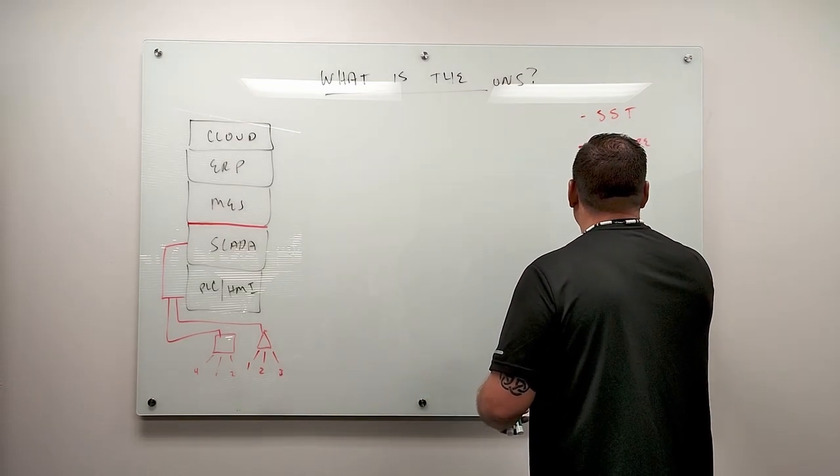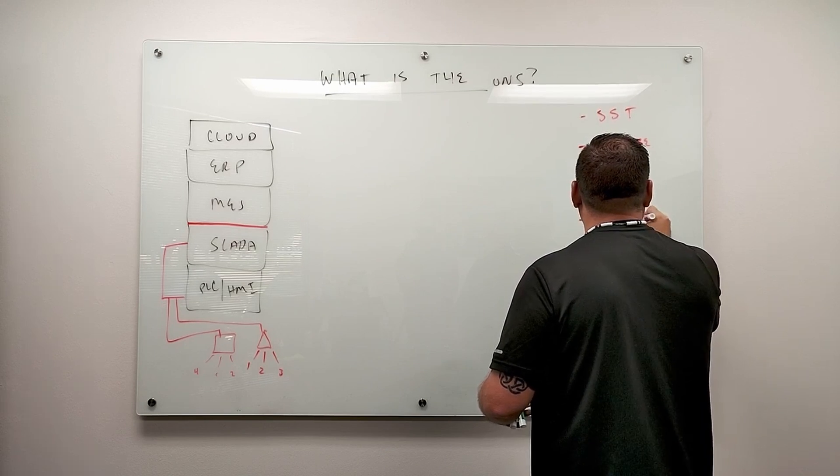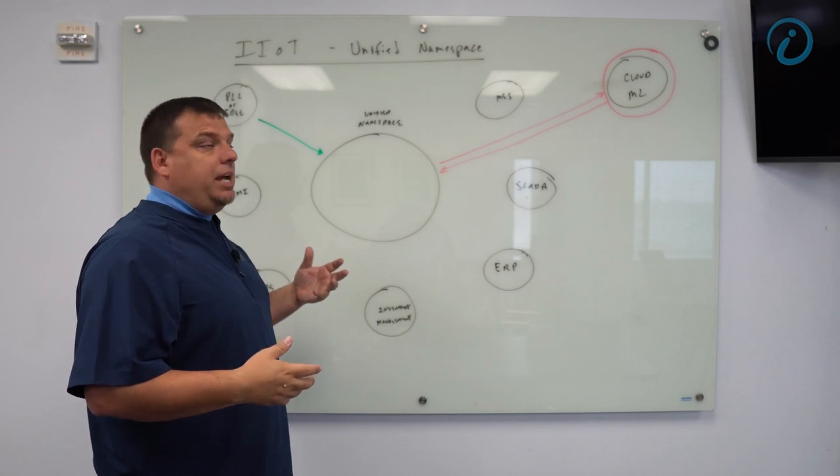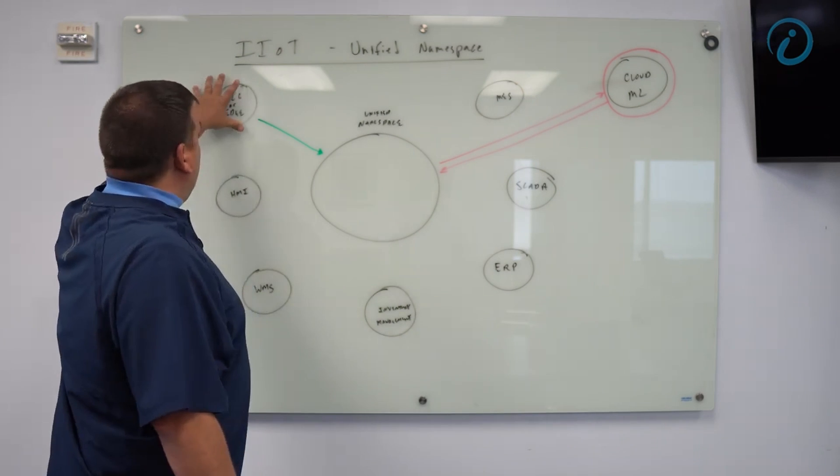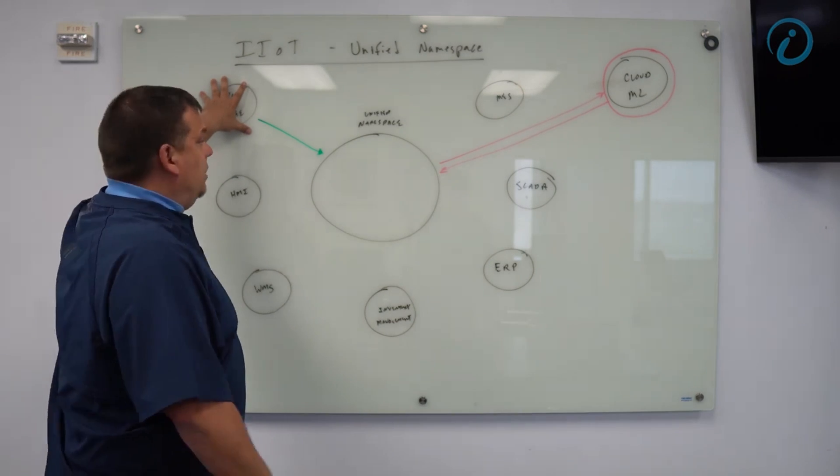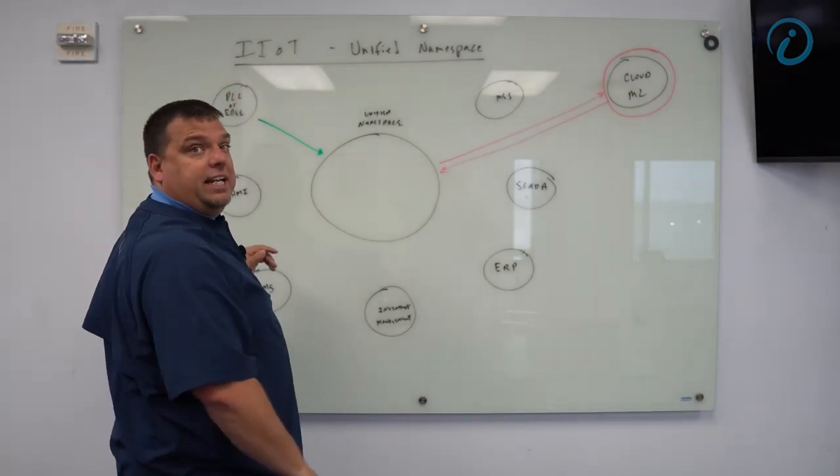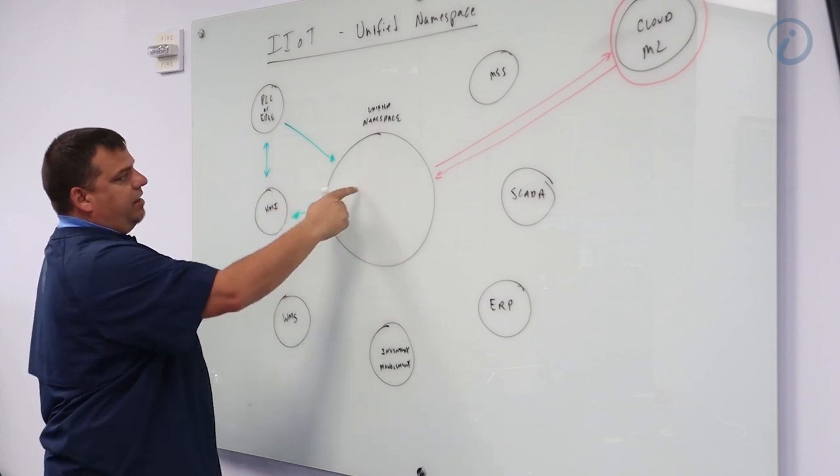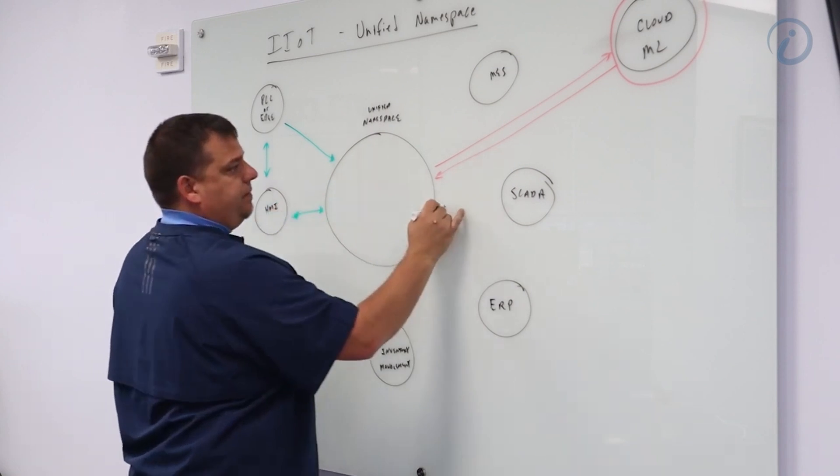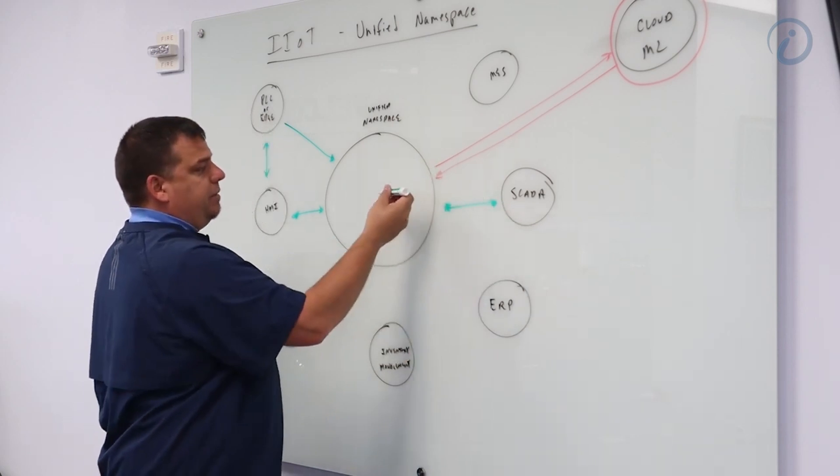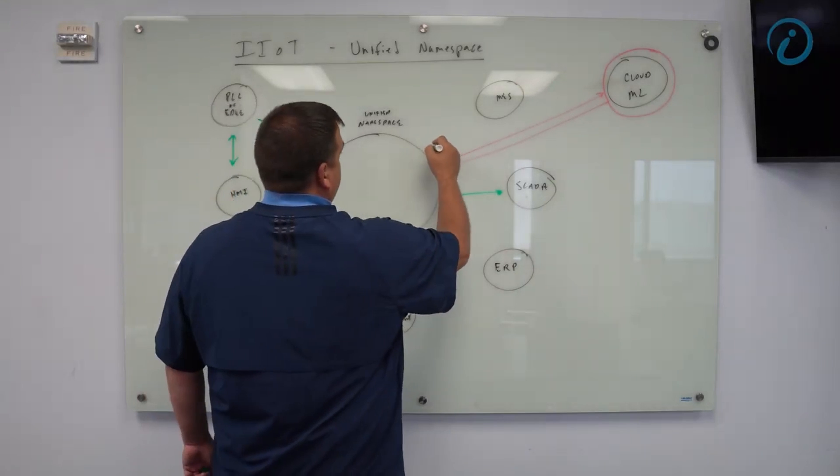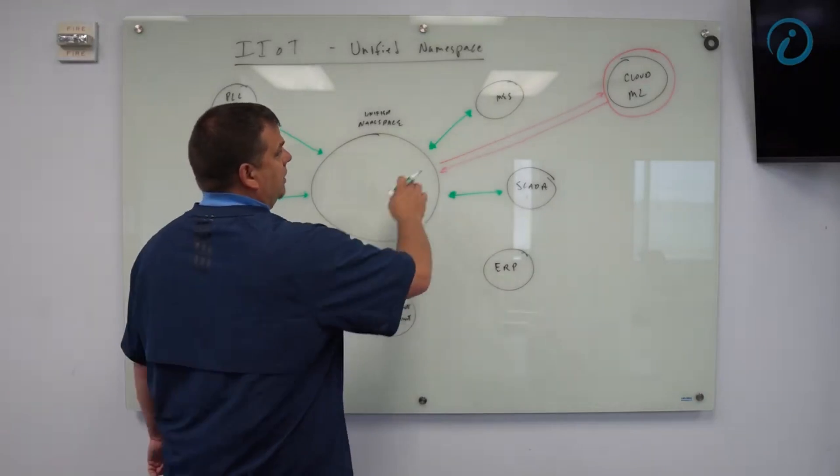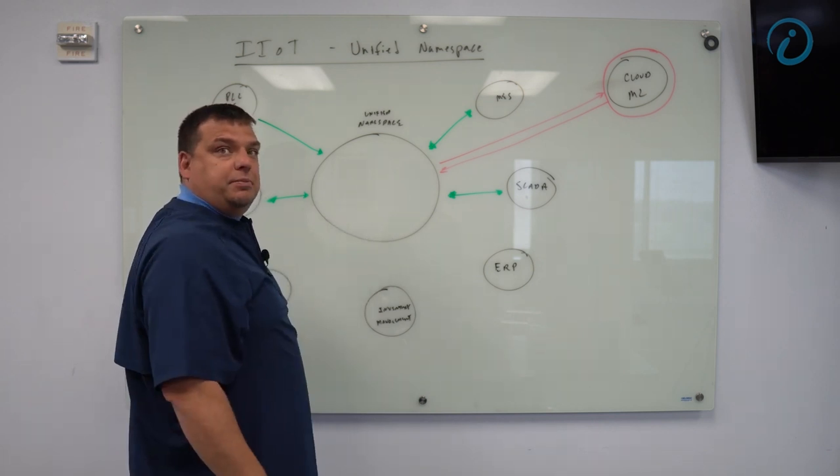And number four, it is the foundation of your digital future. So what we do is we treat all applications, we treat everything in the plant and on the plant floor as a node in the system. So what ends up happening is our PLCs publish their data into a unified namespace. The SCADA system and the HMI get their information from the unified namespace. The SCADA system may process it and then post that information back into the unified namespace. The MES system will then grab its information that it needs to do all of its post processing of data and it will then publish it back into the unified namespace.